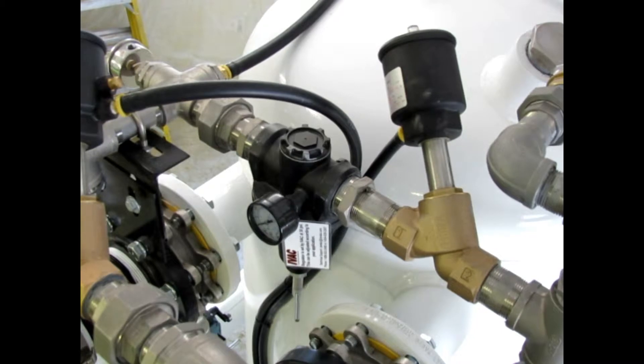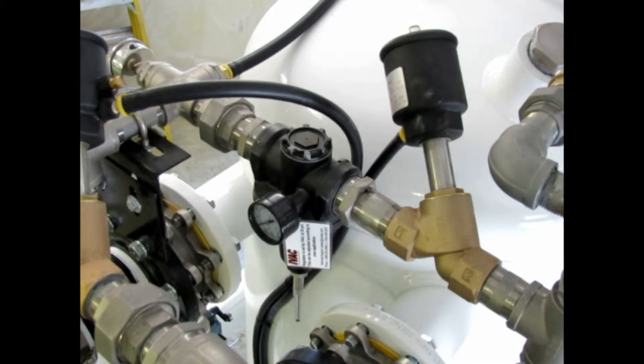This prevents any pressure from reaching the operator's hose. If the unit fails to discharge when on discharge mode, check the intake gate limit switch for correct operation.